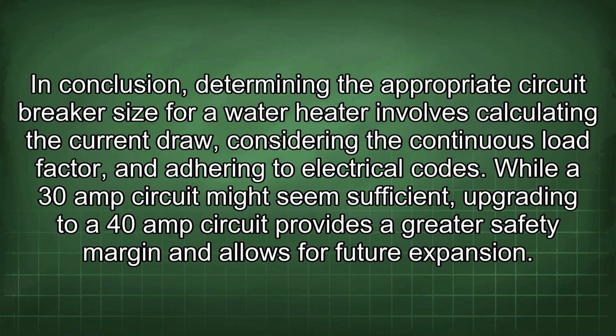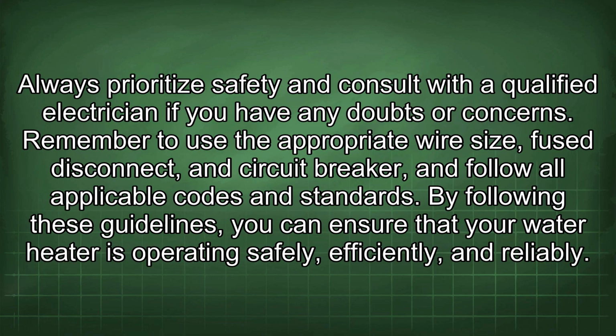In conclusion, determining the appropriate circuit breaker size for a water heater involves calculating the current draw, considering the continuous load factor, and adhering to electrical codes. While a 30-amp circuit might seem sufficient, upgrading to a 40-amp circuit provides a greater safety margin and allows for future expansion. Always prioritize safety and consult with a qualified electrician if you have any doubts or concerns.